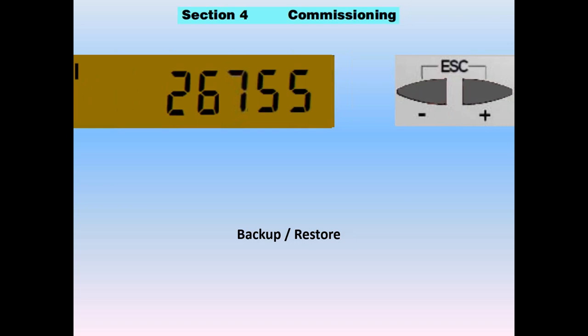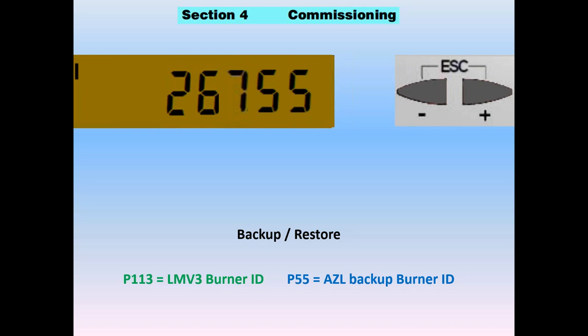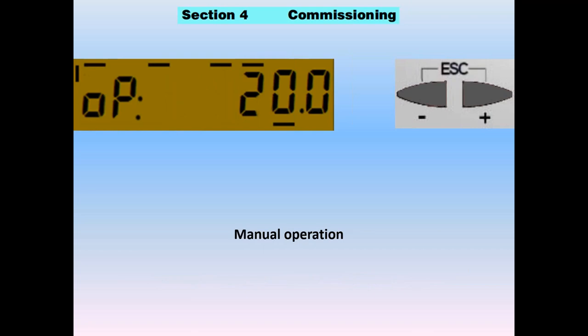Parameter 55 is the burner ID of the parameters in that AZL, telling you which burner those parameters belong to — just like the LMV5. The AZL never runs on its own and can be removed at any time. If you ever do a restore, you get the parameter set gathered from the burner with ID number 26755. If replacing the chassis, you must first enter the same burner ID on the new chassis, then go to parameter 50 and restore — it confirms it's the right burner and restores the parameters.